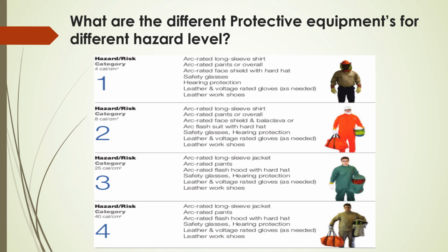What are the different protective equipment for the different hazard levels? Typically, the hazard categories or PPE levels are defined, like level 1. Level 1 hazard risk category is 4 calorie per centimeter square. In level 1 there will be arc rated long sleeve shirt, arc rated pant or overall, arc rated face shield with hard hat, safety glasses, hearing protection, leather and voltage rated gloves as needed and leather work shoes. In hazard category 2, basically the incident energy is 8 calorie per centimeter square. In this category, we use PPE: arc rated long sleeve shirt, arc rated pants or overall, arc rated face shield and balaclava or arc flash suit with hard hat, safety glasses, hearing protection, leather and voltage rated gloves as needed.